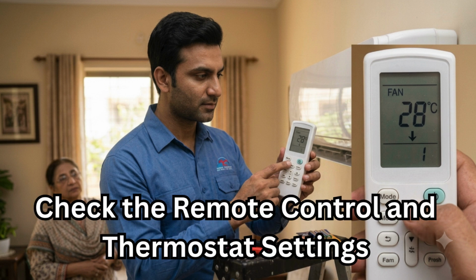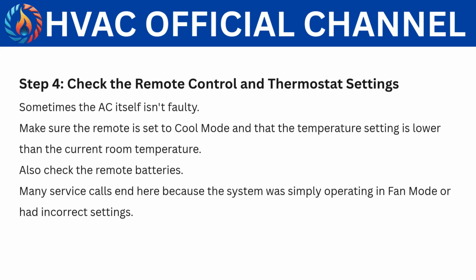Step 4. Check the remote control and thermostat settings. Sometimes the AC itself isn't faulty. Make sure the remote is set to cool mode and that the temperature setting is lower than the current room temperature. Also check the remote batteries. Many service calls end here because the system was simply operating in fan mode or had incorrect settings.